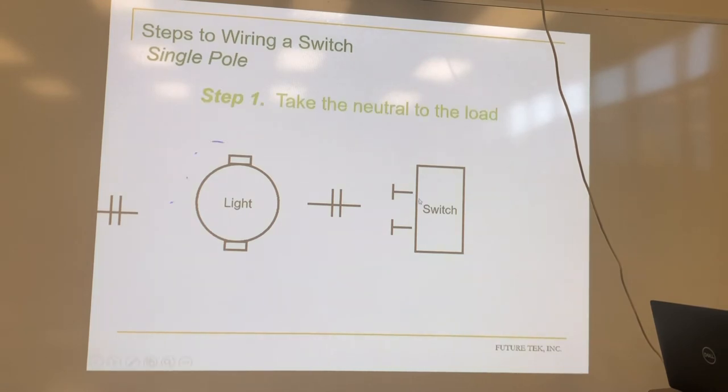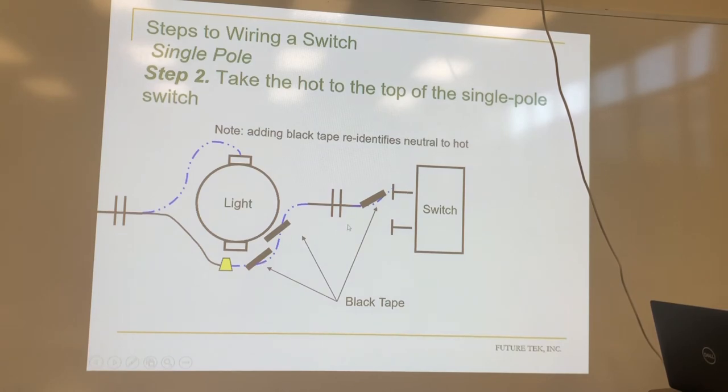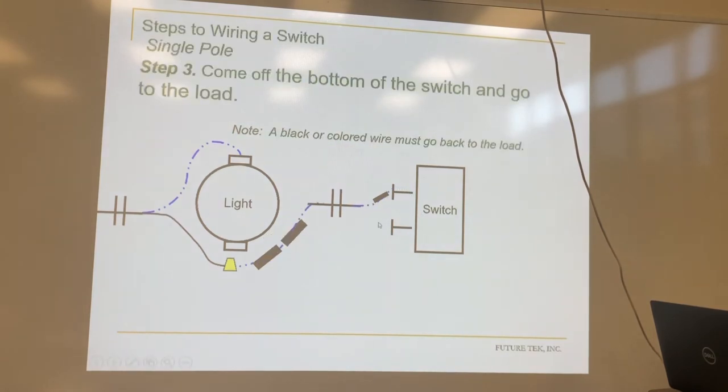So our 12-2 coming in to the light. Our neutrals, obviously, just go straight to the light. This is our hot. It's going to wire nut to the white going to the switch. Okay, but we are going to re-identify this white wire with black tape. You can do that. You can use white wire as a hot, just as long as it's identified with black. So this is our line coming into the switch, right? And then we're going to use the black wire as our load and go to the light. And it makes kind of like a loop. That's why it's called a switch loop, because you're just feeding down to it and back.